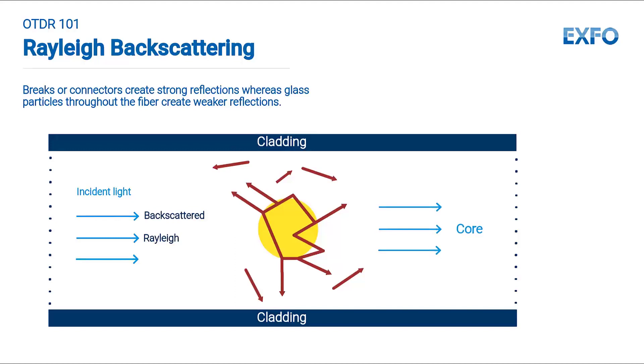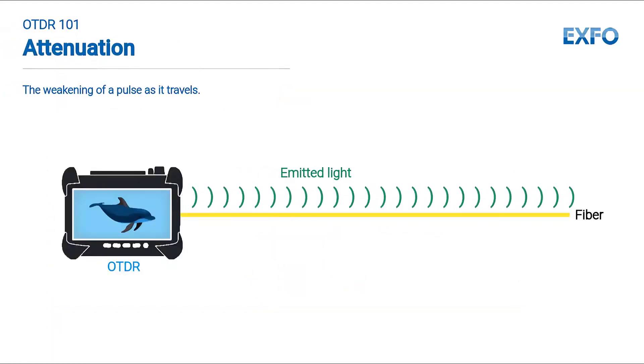Breaks or connectors create potentially strong reflections, but glass particles throughout the fiber also create a little bit of reflection. This is called Rayleigh backscattering, and it is captured by the OTDR. The backscattering reduces as the signal loses energy. The original pulse therefore weakens as it travels — this is called attenuation.